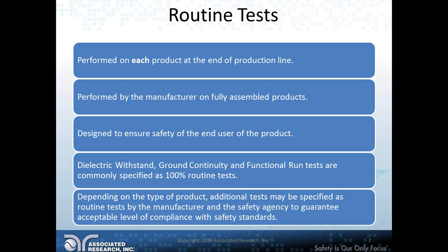Some of the tests that we just looked at, dielectric withstand, ground continuity, and functional run, are commonly specified as 100% routine tests. However, depending on the type of product, additional tests may be specified by the test standard or the manufacturer as routine tests and the safety agency to guarantee an acceptable level of compliance with the safety standard.